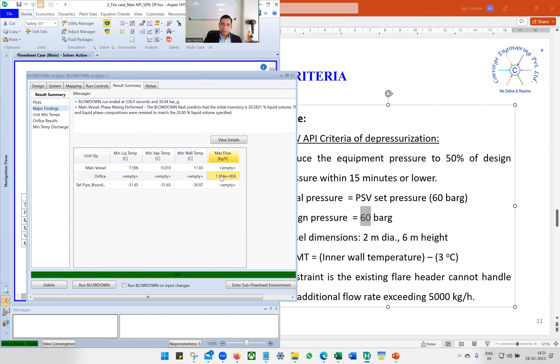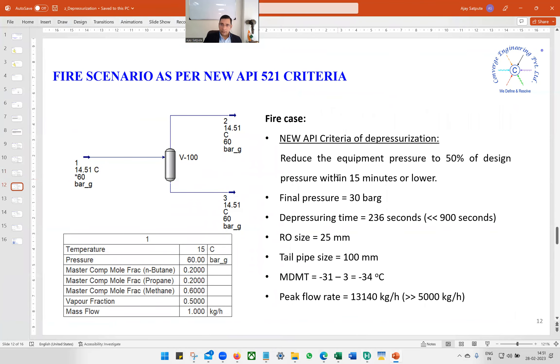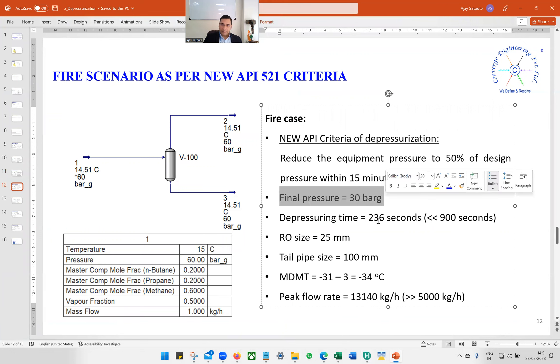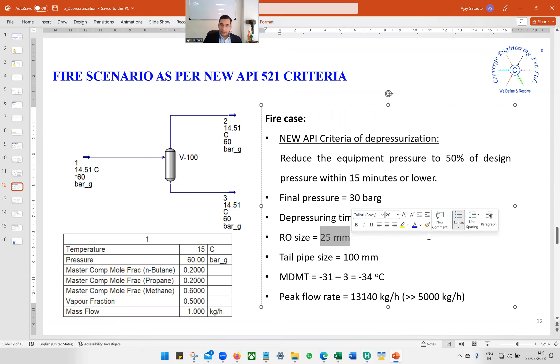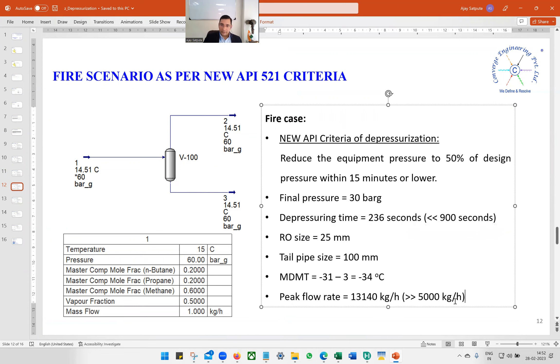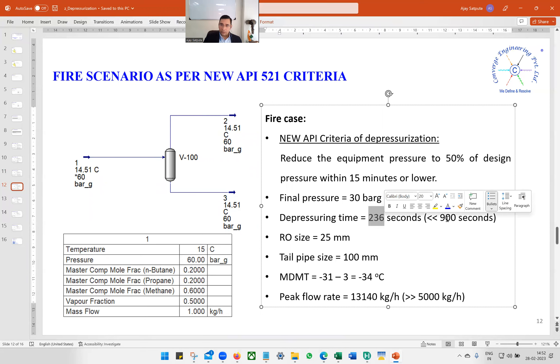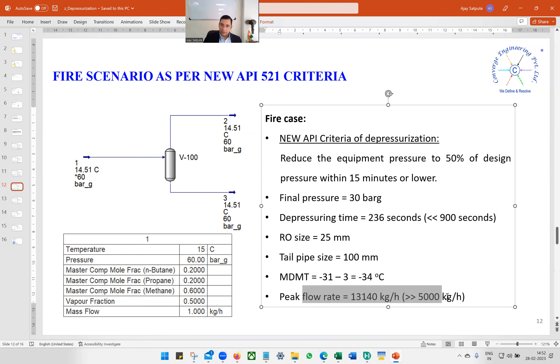The peak flow rate obviously remains the same as Case 1. MDMT would still be minus 31 minus 3, giving minus 34°C. Comparing Case 2: final pressure is 30 bar gauge, depressuring time is 236 seconds. Since the depressuring time is only 236 seconds, there is margin to reduce the RO size and thereby reduce the peak flow rate — hopefully without exceeding 900 seconds — because the target is to keep peak flow below 5000 kg/hr.